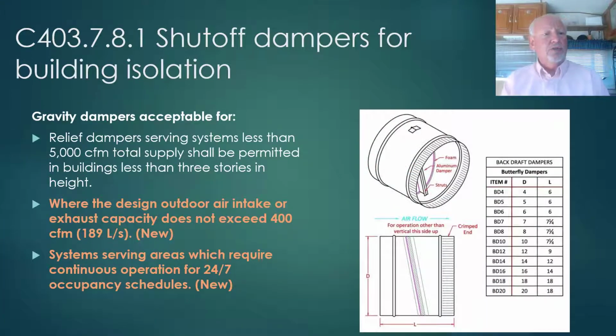And then some control of shut-off dampers for building isolation. New automatic or motorized dampers have been a control requirement in the code, and that's been problematic, especially on small systems. And so there have been some revisions to this requirement where gravity dampers, non-motorized dampers, are acceptable for outside air intakes or exhaust capacities that do not exceed 400 CFM regardless of occupancy. This was previously limited to Group R occupancy only, but that Group R restriction has been removed.